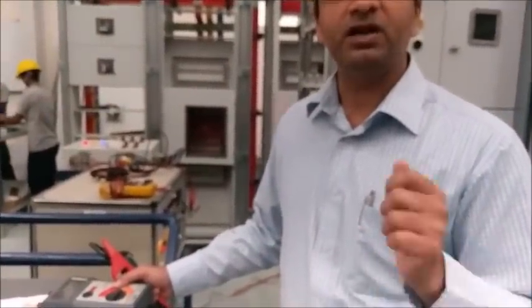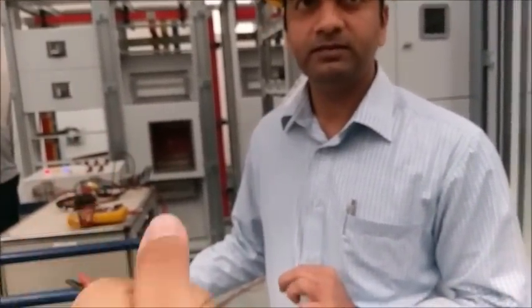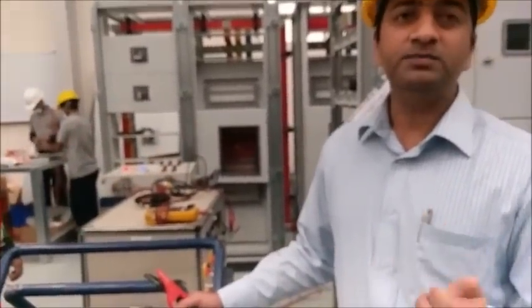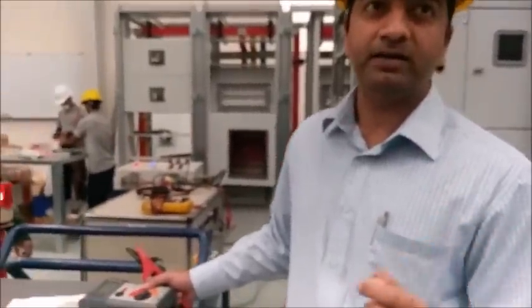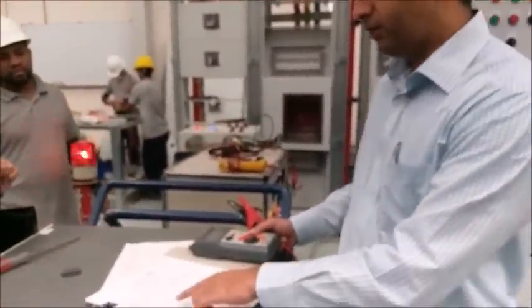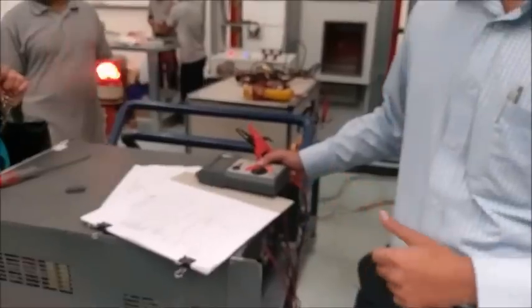And if tripping, you are making the function on, off, tripping, like this, you are pressing this button. I think it's an orange button. Yeah, the orange button is for trip for the ACB. For MCCB, it's the white button. And for electrical functions, we have to energize the panel.